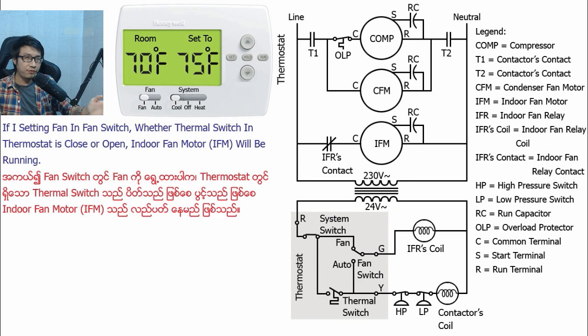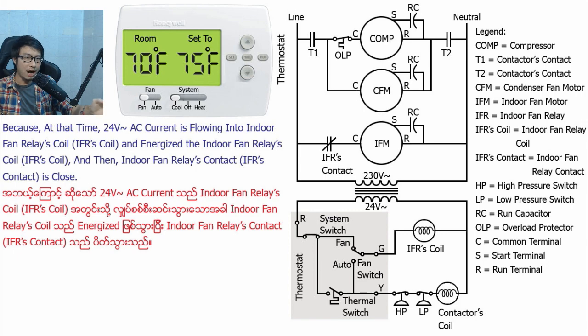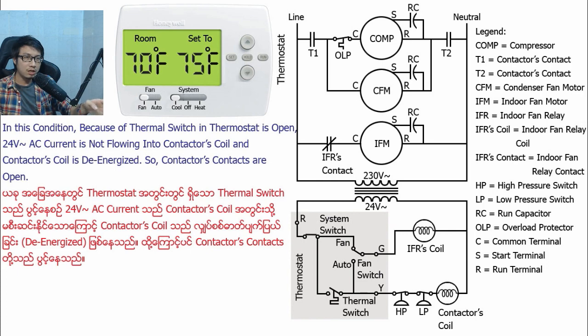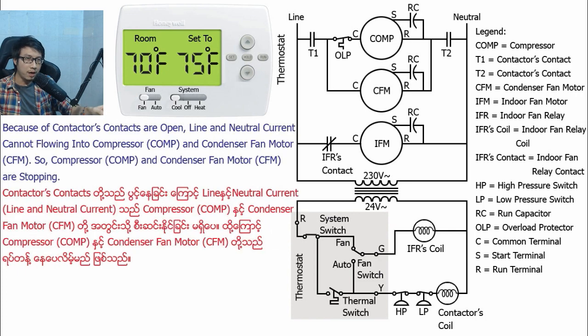If I set the fan switch to fan-on, whether the thermal switch in the thermostat is closed or open, the indoor fan motor will be running. Because 24V AC current is flowing into the indoor fan relay coil and energizing it, the indoor fan relay contact closes, and line and neutral current flows into the indoor fan motor, so it runs. In this condition, because the thermal switch in the thermostat is open, 24V AC current is not flowing into the contactor coil and the contactor coil is de-energized, so the contactor contacts are open and line and neutral current cannot flow into the compressor and condenser fan motor.